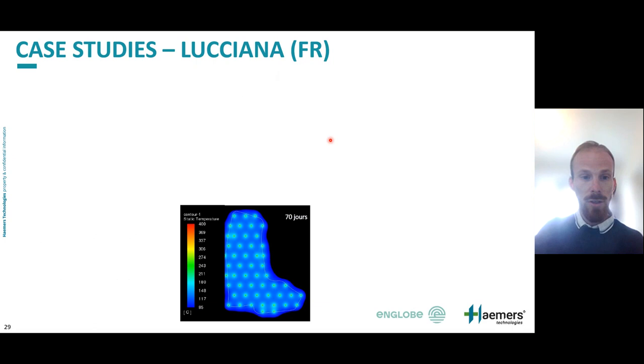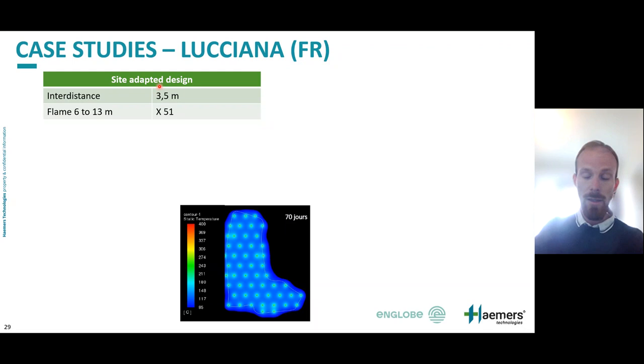We also did a modelization. So here you can see a modelization of the heating of the site. You can see that with the interdistance that we chose of 3.5 meters, we could reach the 85 degrees target temperature in 70 days.